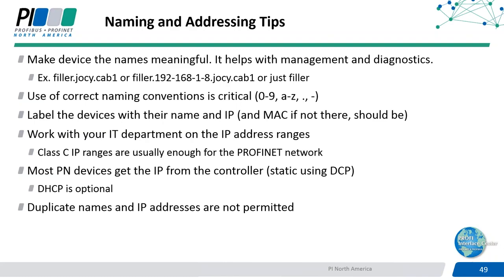Work with your IT department if you have to on the IP address ranges. Typically for PROFINET, Class B or C is used since that's usually enough unless you're getting into really large networks. Keep in mind most PROFINET devices will automatically get their IP addresses from the controller based on the configuration, using what we call the PROFINET DCP protocol. We don't really use DHCP since that's dynamic addressing—it's optional, and some devices may support it, but most of the time they'll get their IP address from the controller. So that's a discussion you probably want to have with your IT department about what ranges to use out in the plant versus the office, because duplicate names and IP addresses are not permitted. If you're interconnecting devices with the office too, you have to make sure there are no duplicates of names or IP addresses.